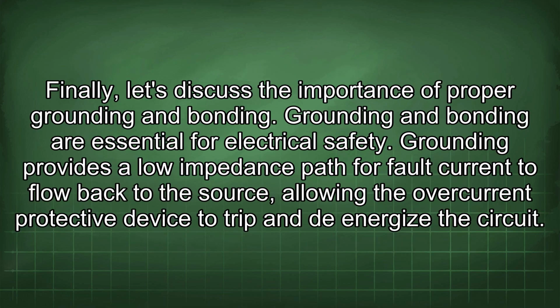Finally, let's discuss the importance of proper grounding and bonding. Grounding and bonding are essential for electrical safety. Grounding provides a low impedance path for fault current to flow back to the source, allowing the overcurrent protective device to trip and de-energize the circuit.